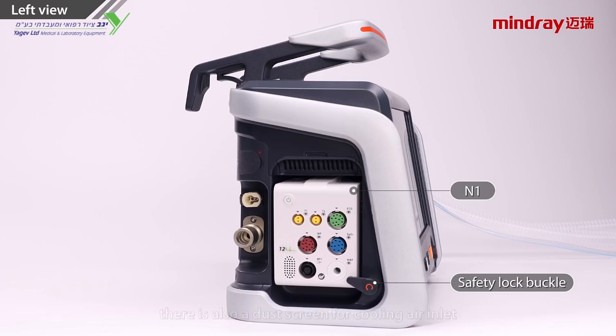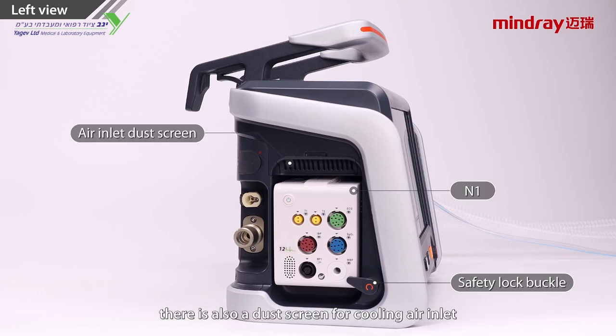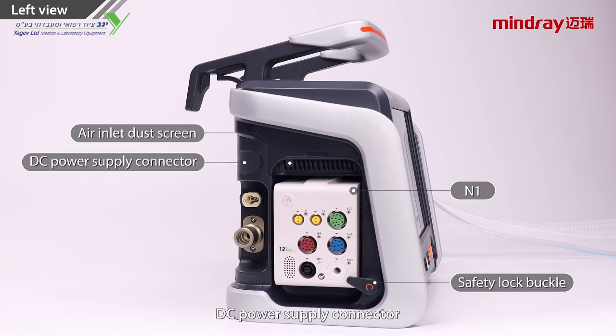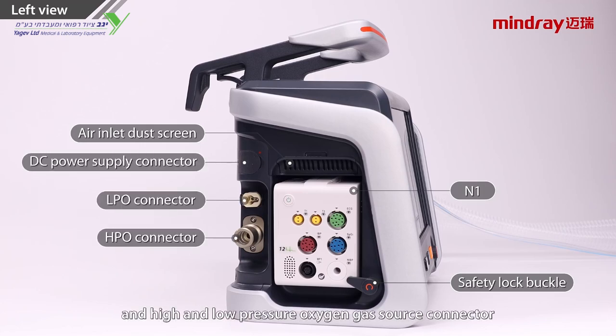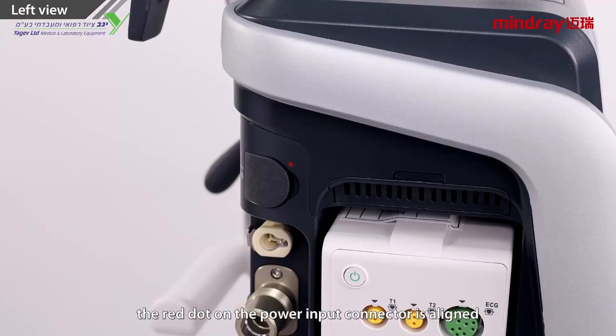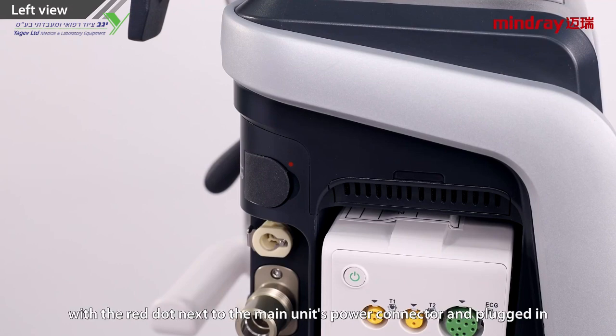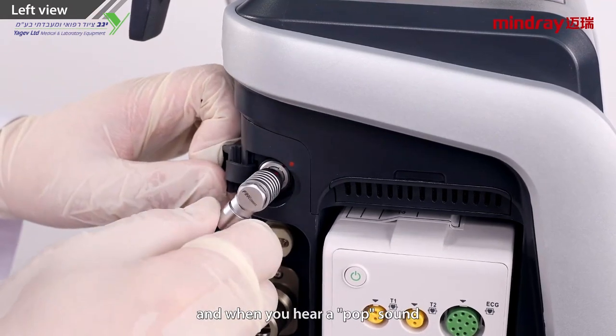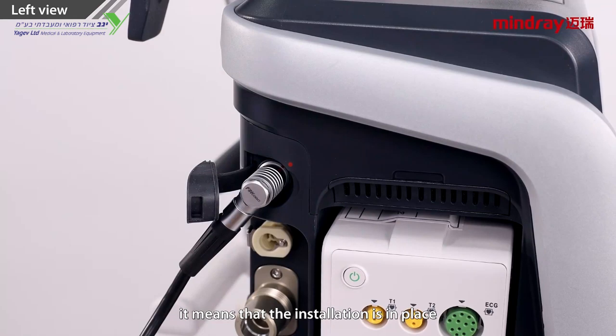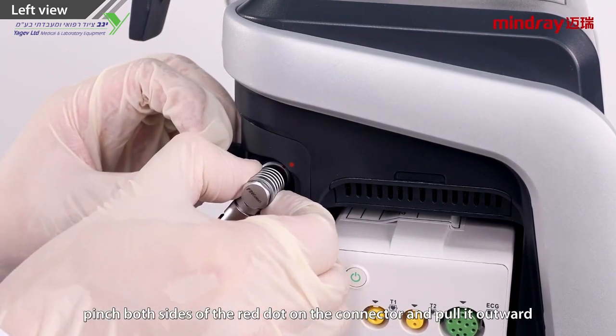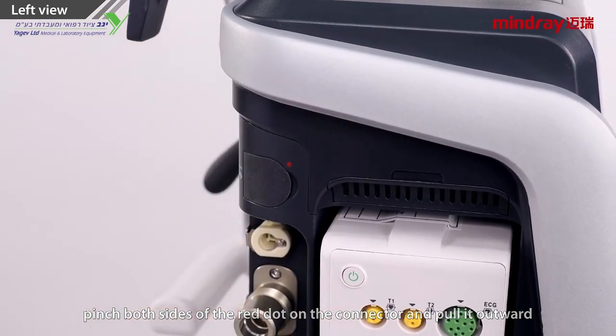On the left side there is also a dust screen for cooling air inlet, DC power supply connector and high and low pressure oxygen gas source connector. When connecting, the red dot on the power input connector is aligned with the red dot next to the main unit's power connector and plugged in, and when you hear a pop sound, it means that the installation is in place. When unplugging the DC power input connector from the main unit, pinch both sides of the red dot on the connector and pull it outward.